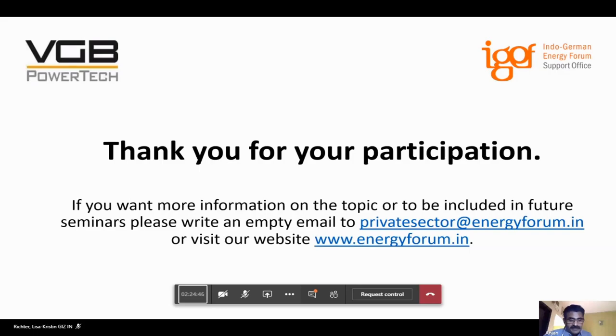Okay. So then the next question is, does the cost of startup include oil consumption or work? No, it's not. There are two costs involved in that, what I had shown in the initial slides. One is your life consumption. You're consuming some life of the machines, meaning fatigue and creep life. And the other thing is your EFOR, because with each startup, you are increasing a very small, maybe a micro percentage of your EFOR. EFOR means equivalent forced outage rate, that will increase. So it's mainly life consumption cost. Oil cost is different. It's not included in this cost.